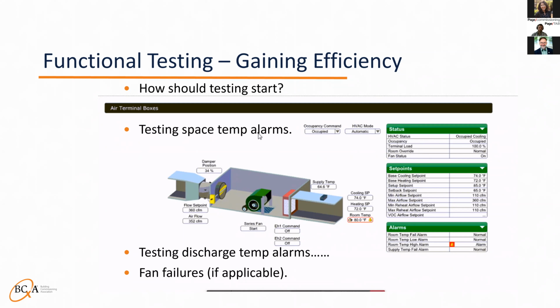Testing space temp alarms. If the building is occupied, and this may be obvious, but do not try to cool or heat the space to trip the alarm. People will get uncomfortable. Instead, try adjusting all high temp alarm set points below the current temp reading and adjust all low temp alarm set points above the current temperature reading. Also consider changing the alarm time delays for the purpose of testing, then putting them back to their original value.